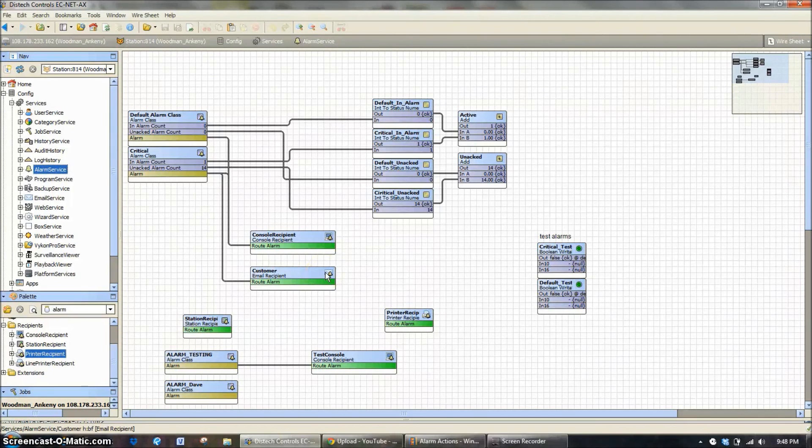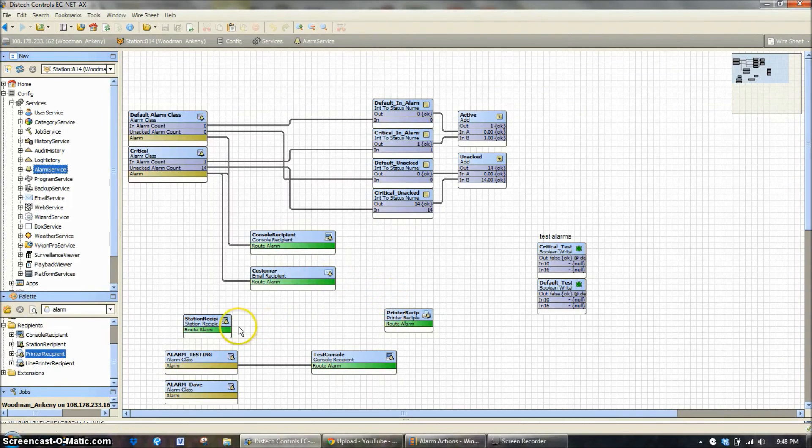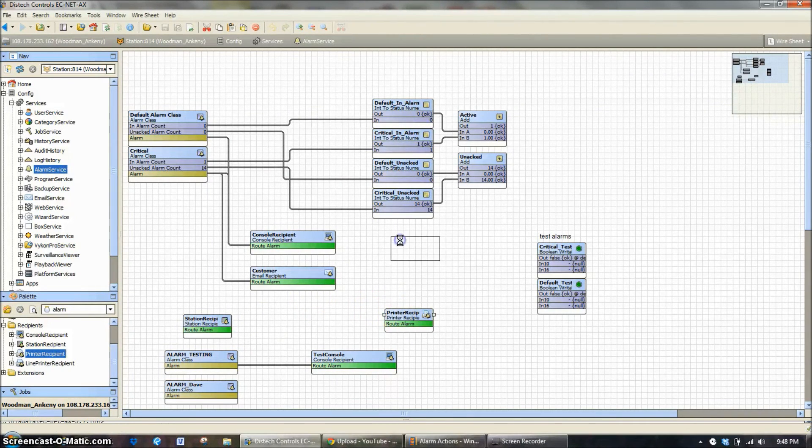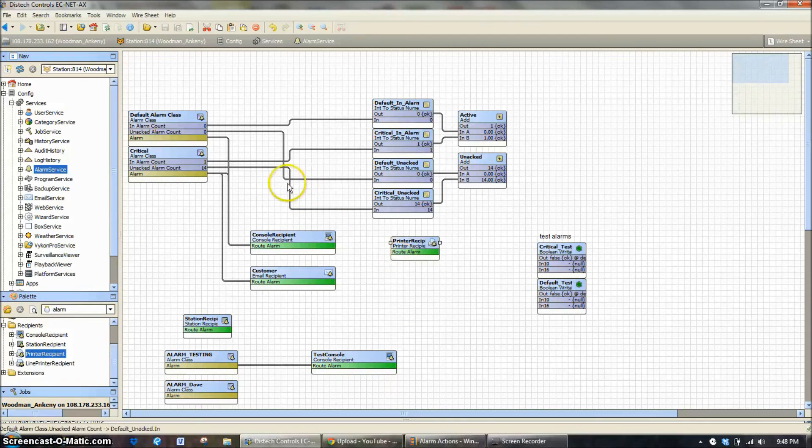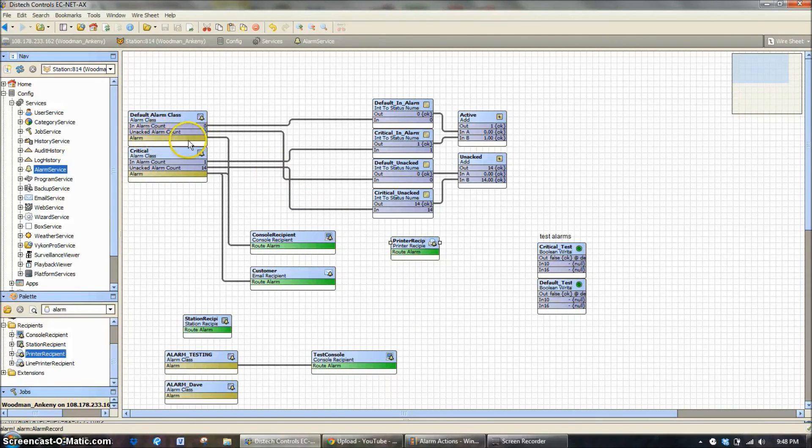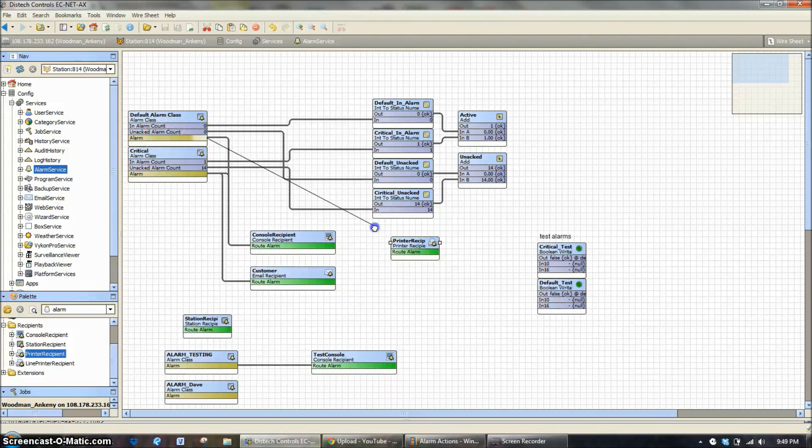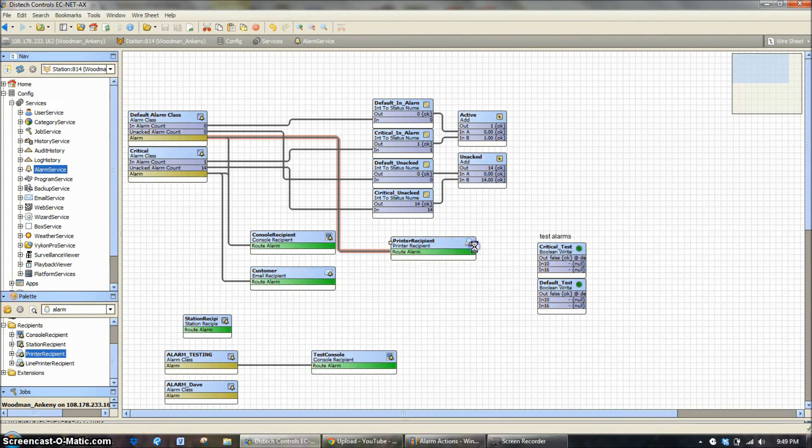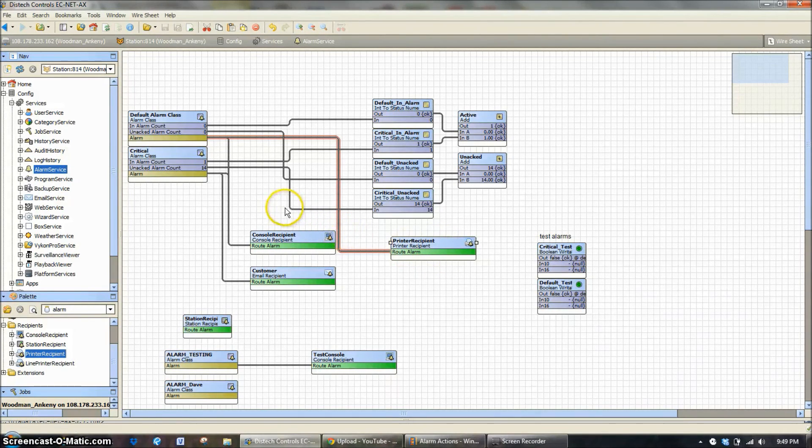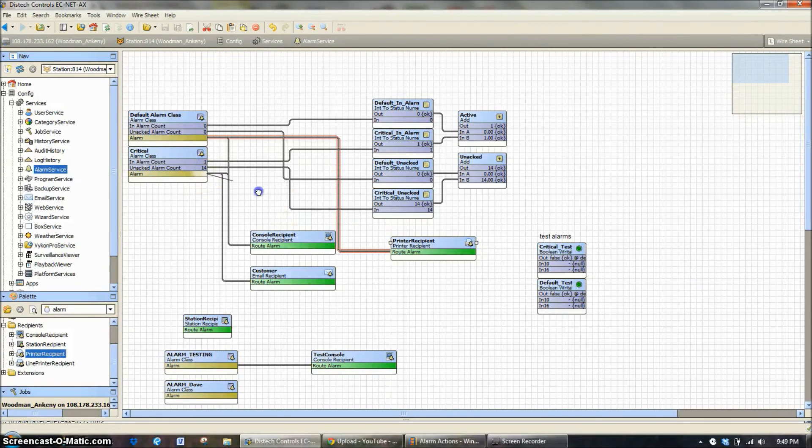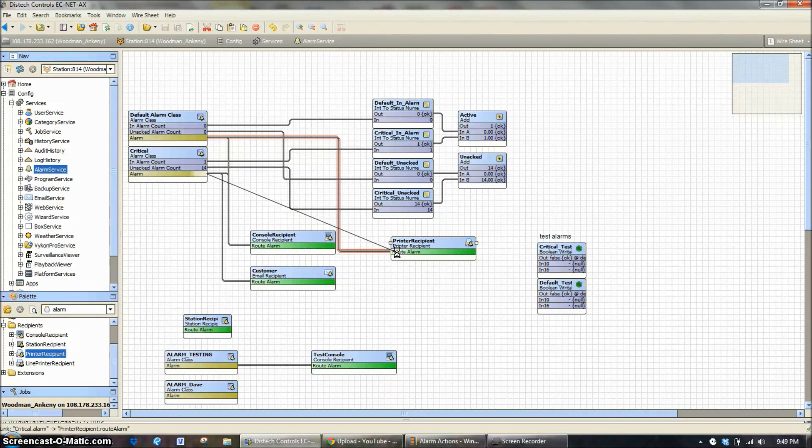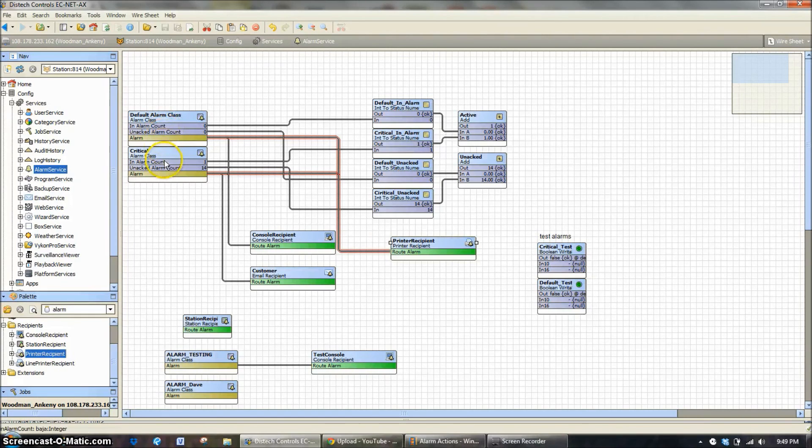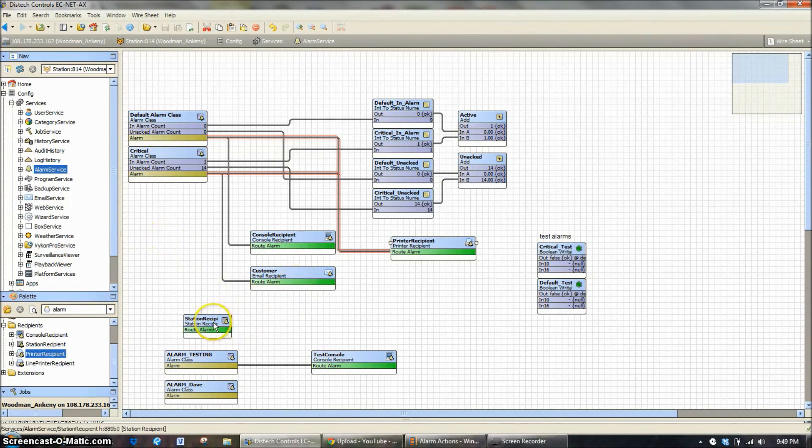Now, once you get the configuration and have the printer or station recipient or customer block on the screen and configured the way you want it, it's really simple to hook it up to what alarm class you want to monitor. So in the alarm output, it's simply a click and drag, and now all my default alarm class alarms will be routed to this printer. So this printer is going to print all those items. If I want to print more than that, like I want to print the critical alarms as well, I can hook multiple lines up to that one device. So that's how you would hook up and have the printer recipient print all the default alarm class and all the critical alarm class alarms. It would be the same process for an email recipient or a station recipient.